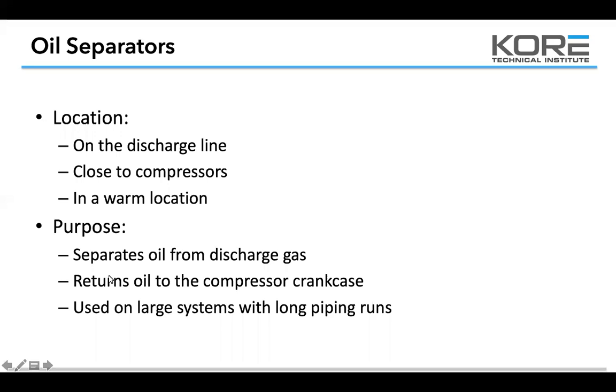The purpose of the separator is obviously to separate the oil from the discharge gas and return it to the compressor crankcase. It's used on large systems with long piping runs. Depending on the rack, you'll still see crankcase heaters on those compressors. Those crankcase heaters should be energizing in the off cycle — that keeps the oil warm and helps boil off any liquid refrigerant that may migrate to the compressor. You want your crankcase heater energized when the compressor is not running, not when it is running.